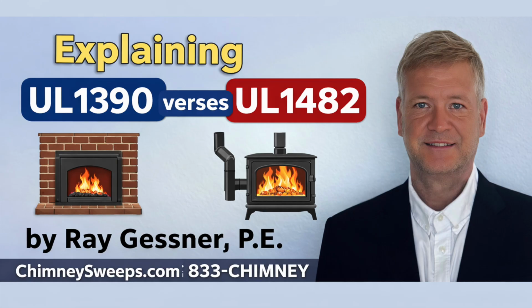Because safety regulators cannot afford generalized math when material science is involved. The failure points of a massive brick chimney are fundamentally different from the failure points of a factory-built metal fireplace. Let's follow that logic. A masonry fireplace is essentially a giant thermal battery. It absorbs the heat slowly over hours, right? Yes, the mass of the stone manages the thermal load. But a factory-built fireplace is typically made of thin sheet metal, and it's usually installed directly inside the combustible wood framing of a house, the 2x4 studs. And thin metal conducts heat almost instantly.